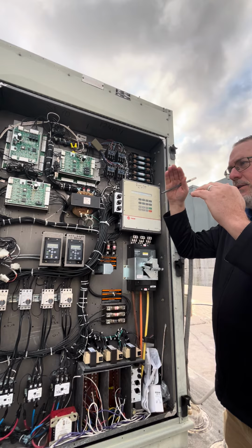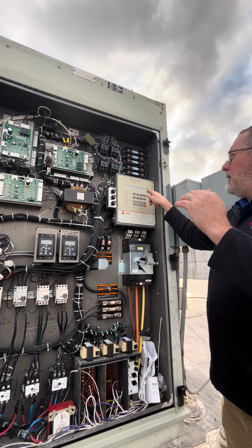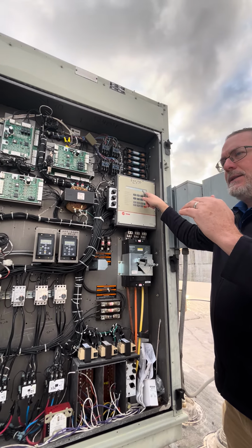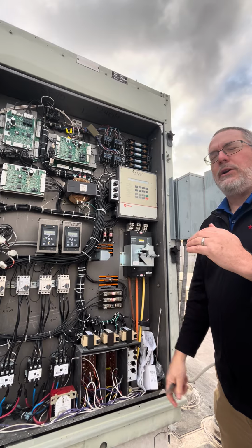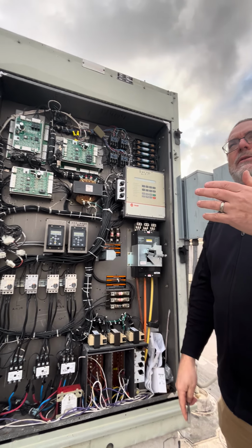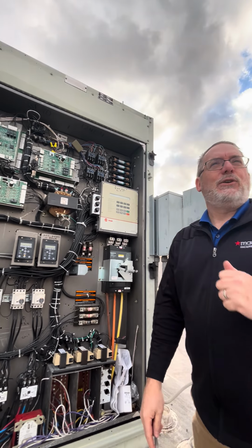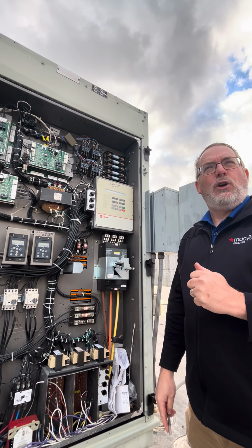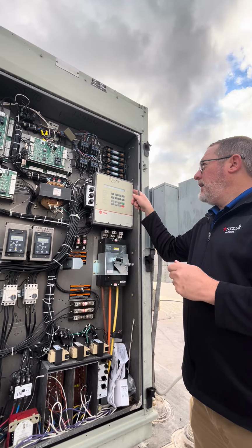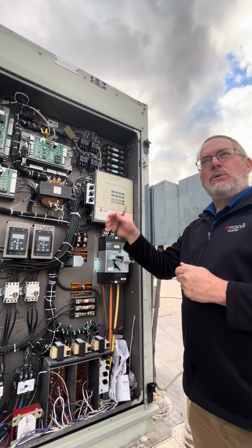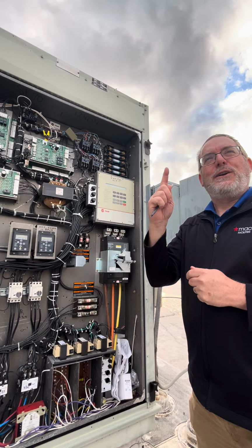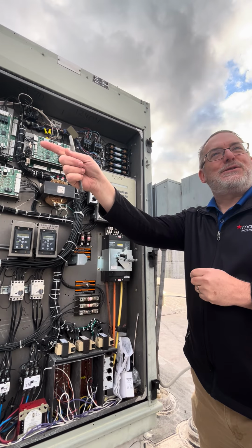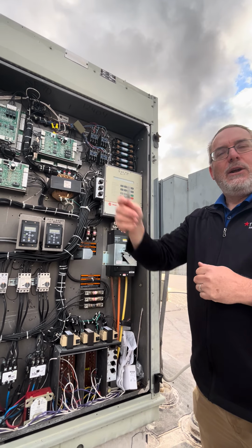This is coming down to 50. Let's release this at 50 degrees, release mechanical cooling to run, let's say at 73.7 degrees, a couple tenths before 74. Let the cooling run. So now I'm going to get 50 degrees coming off this unit with maybe only one compressor because my VFD is running at 30 or 40%. Because it's too slow. Real slow.